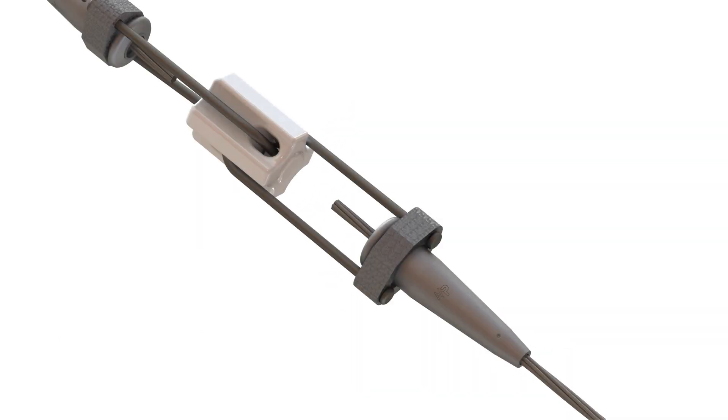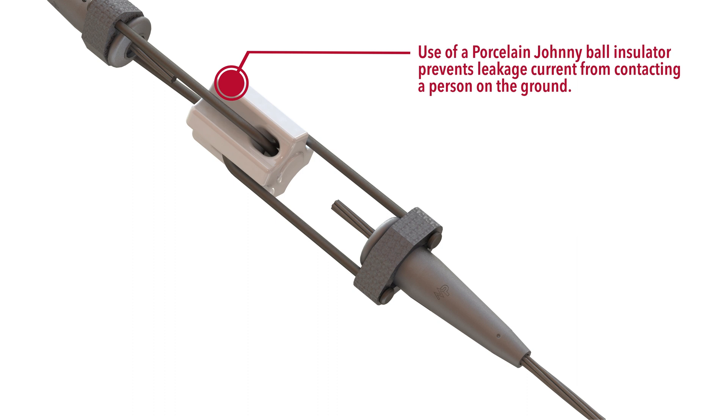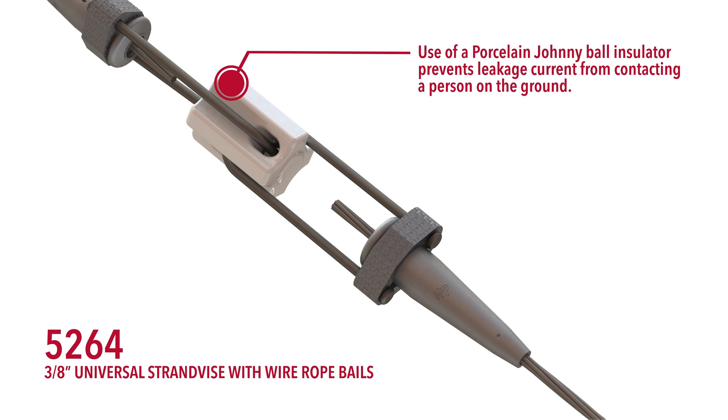The National Electrical Safety Code requires ungrounded guys to be insulated. Using the porcelain Johnny Ball insulator for this prevents leakage current from contacting a person on the ground. Our universal Strandvises with wire rope bails, like these 5264s, can be used for this application, as shown.